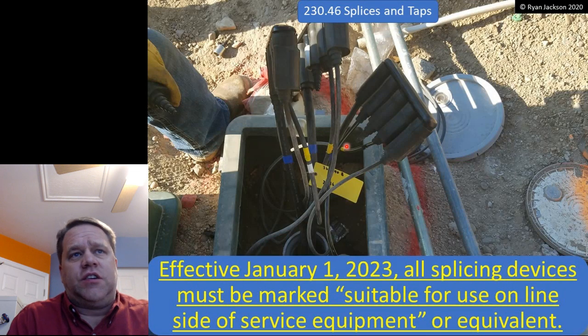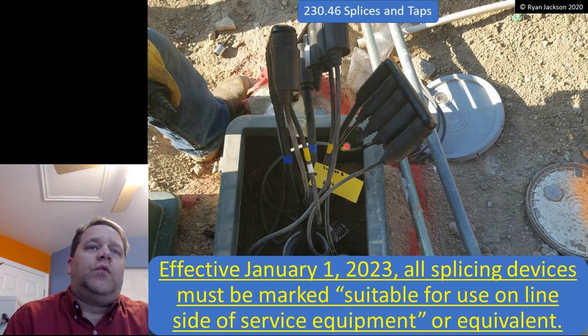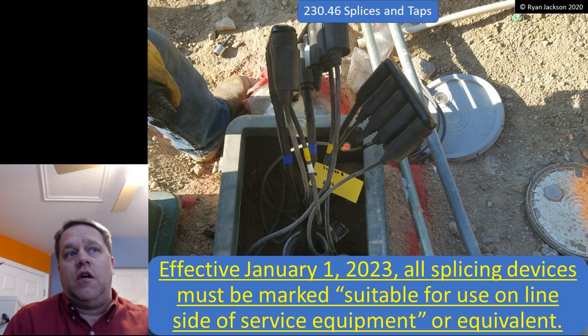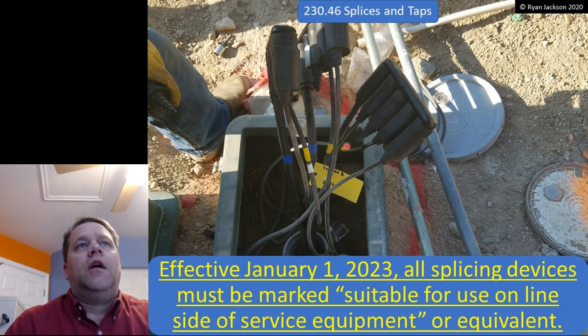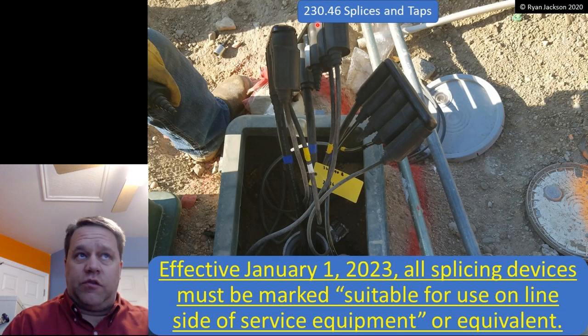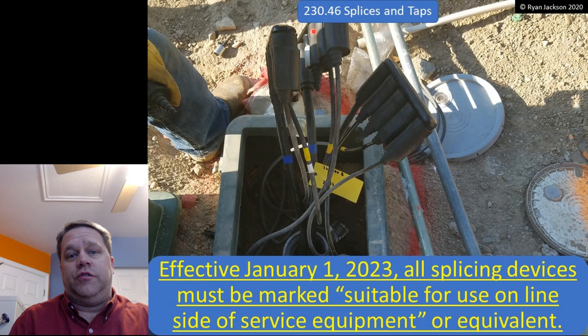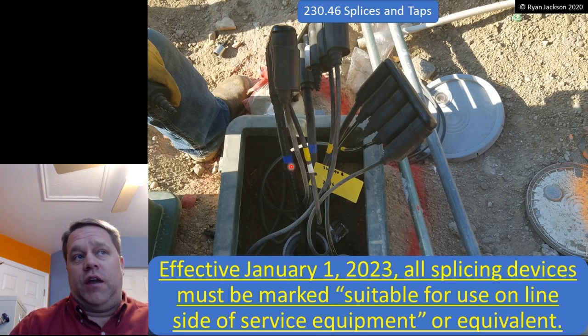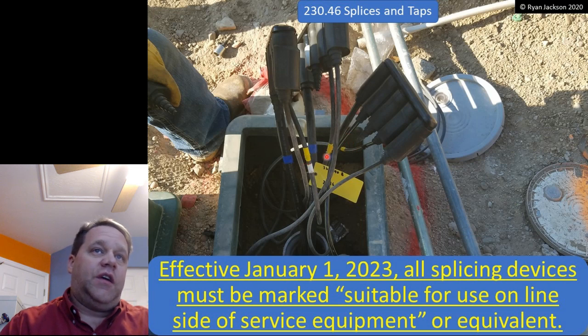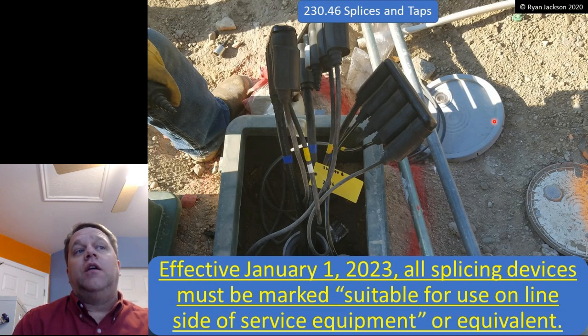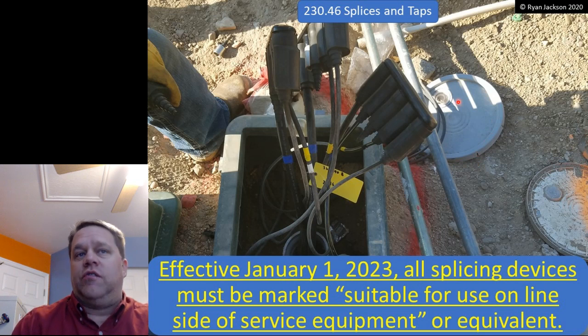The other thing that changed in this section is effective January 1st of 2023, all splicing devices must be marked suitable for use on the line side of the service equipment or equivalent. Now again, we're in Article 230, so let's make sure that we're talking about conductors under the scope of Article 230. It's not every splicing device, it's splicing devices for service conductors. So if these conductors are regulated by the NEC and they're on the line side of the service, then these splicing devices have to be what? They have to be listed, and in 3.5 years from now, they'll have to be marked suitable for use on the line side of the service or equivalent.